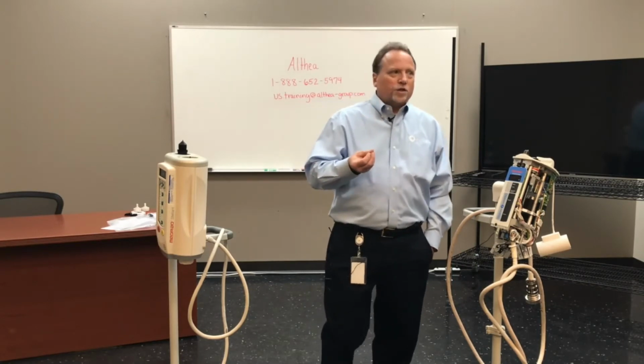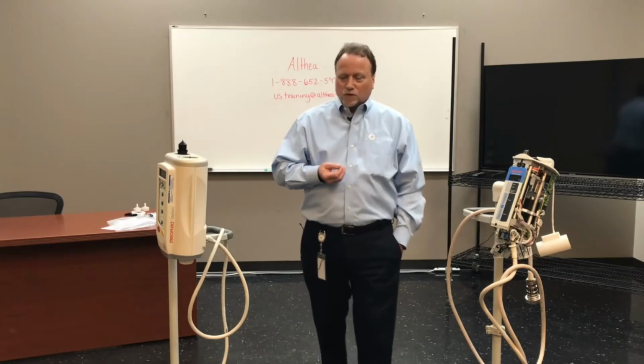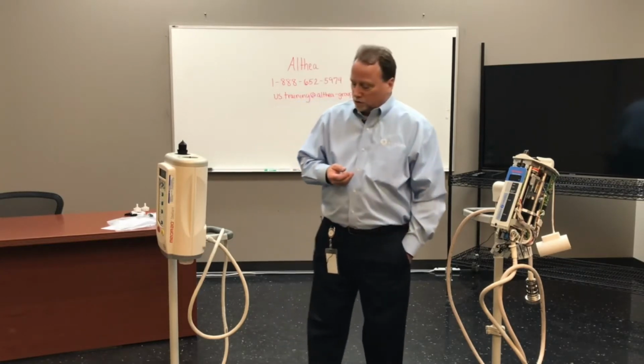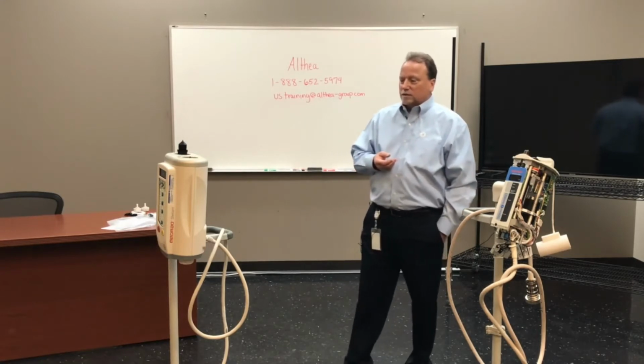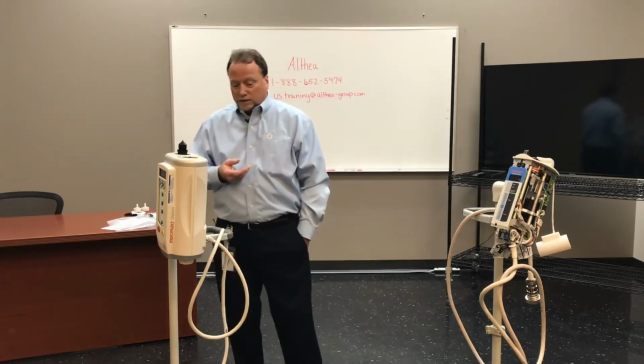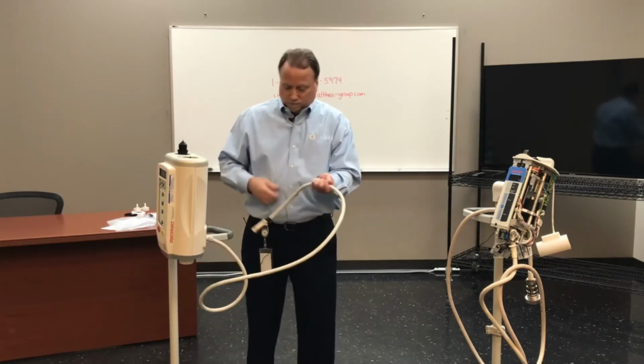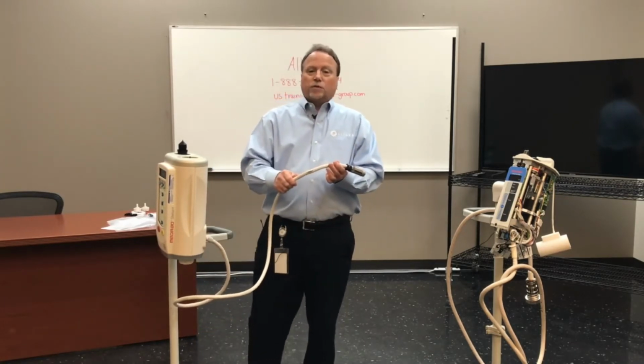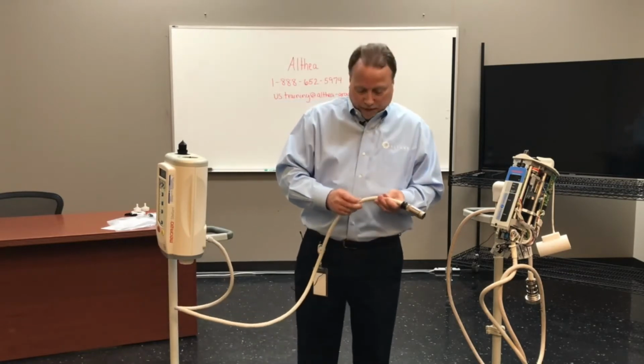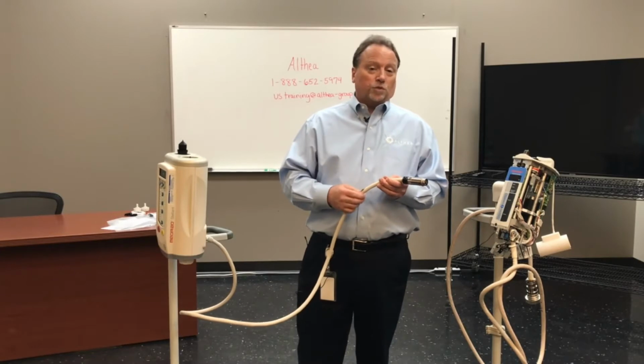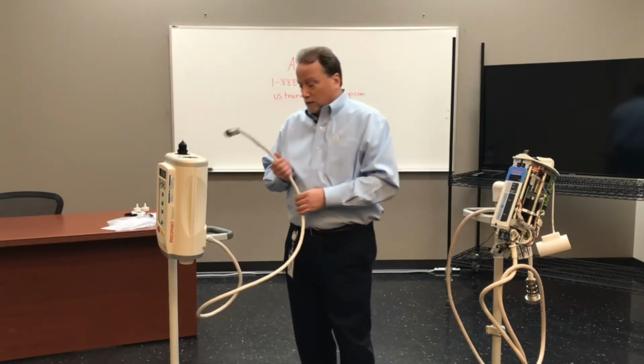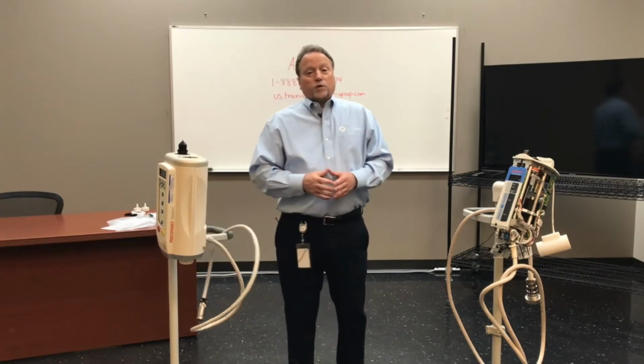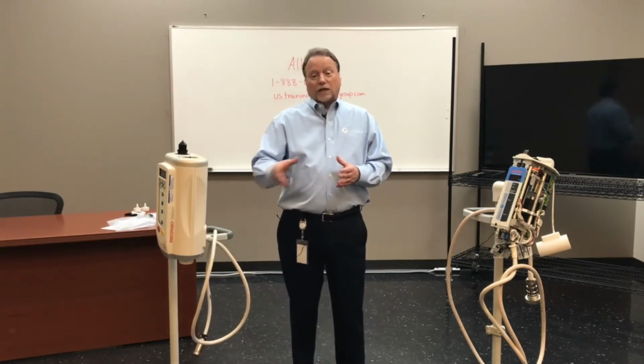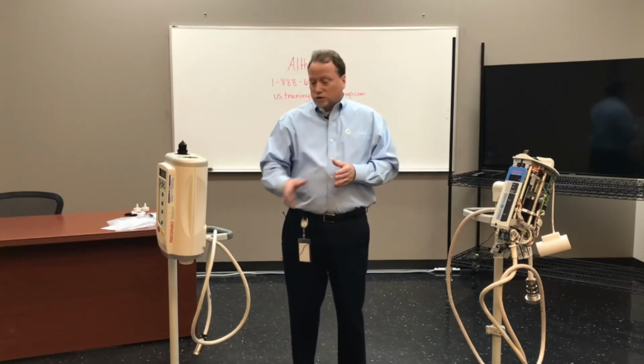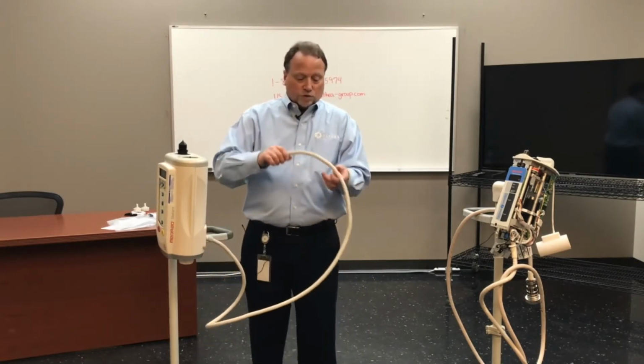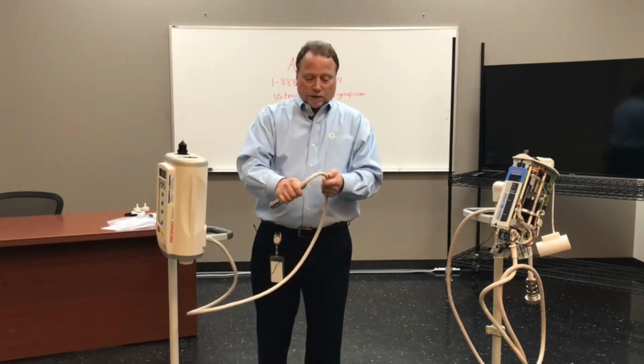Once you do that, then you want to go ahead and do an initial inspection. With that inspection, you want to take a once-over to see if there's anything that could be dangerous to you, such as on this one. Bad cable. It wasn't there when you first looked at it, but now there's a cut in that cable. So are you going to do the PM, or are you going to order the head cable? Well, I would order the head cable and postpone the PM, because that could be a problem. I would actually deadline this and say, Mary Jane, you can't use this. This is an issue. This is a safety risk to the patient and to anyone else. This has to be replaced.